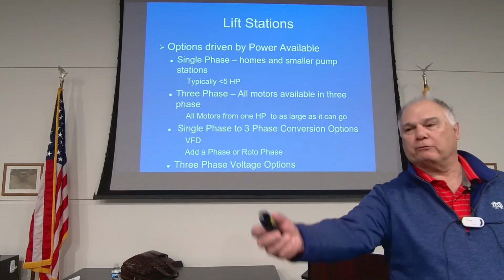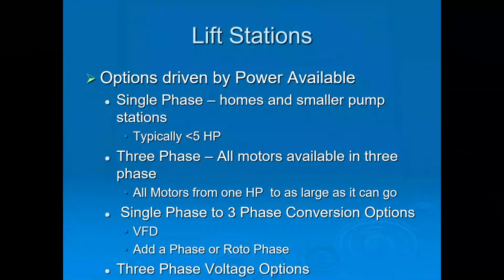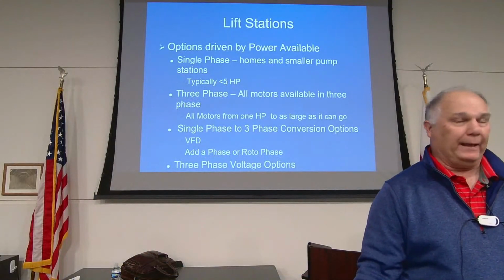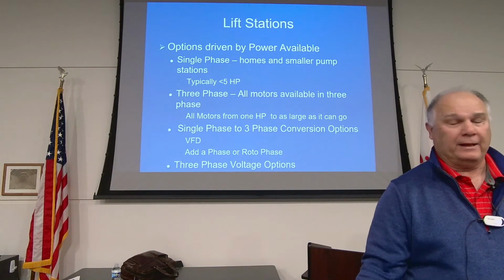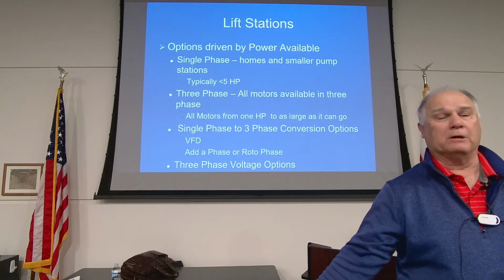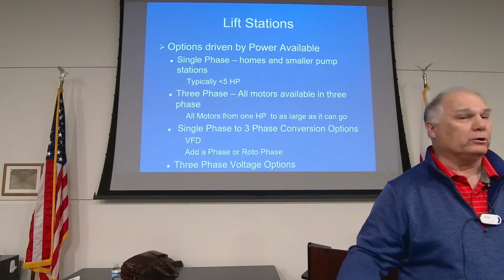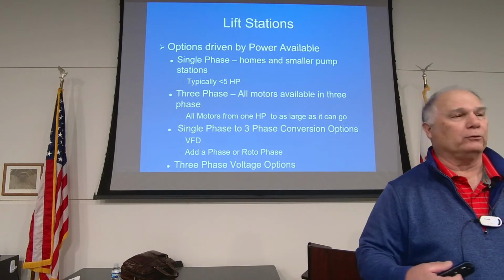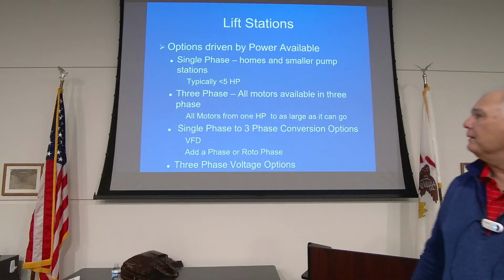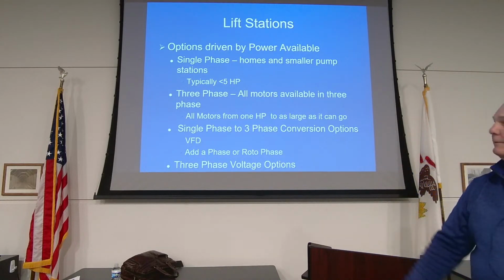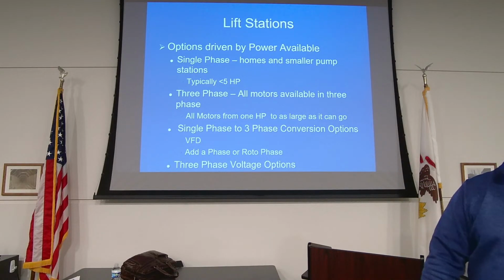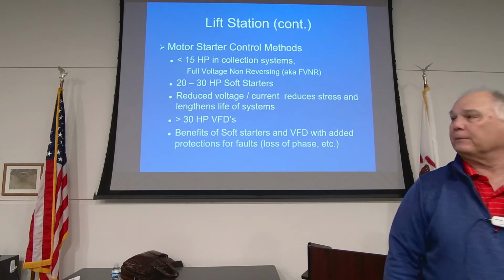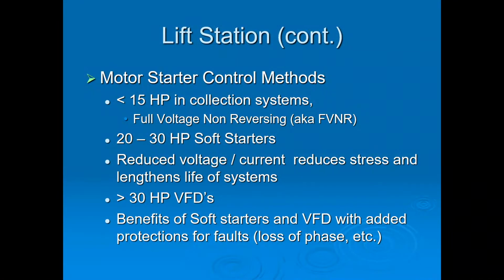Single phase pumps, usually grinder pumps. Small non-clog pump stations are available single phase, depending on what power you have available. Don't do any single phase pumps over 5 horsepower. They don't make them very often. If they do make them, it'll be 9 months before you get the pump. So you can convert that voltage from single phase to 3 phase and do a regular size motor for that. With 3 phase, 230, there's less 208 available today. But 230, 480 is typically what we usually have. And anything 20 horsepower and up, we suggest soft starts.